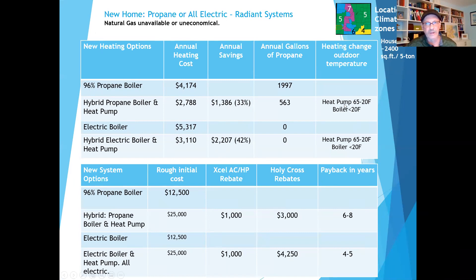With the hybrid model — if I put in an electric boiler — the changeover is around 20 degrees because of capacity. With nice rebates and good savings, the payback is six to eight years worst case, under 10 years. Some clients think that's a long time; other clients find six to eight years very acceptable.